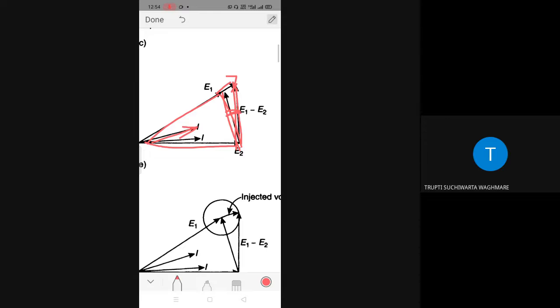The angle of E1 changes significantly. The angle of the voltage drop across the line, that is E1 minus E2, changes significantly. So because of this, what happened? As we know, the current flowing through the line is in quadrature with the voltage drop across the line. So because the phase of E1 changes, the change in the magnitude of I is slight, but the change in the phase angle of I is significant. And as the change in the phase angle of I is significant, it is causing a significant change in the reactive power flow through the line.